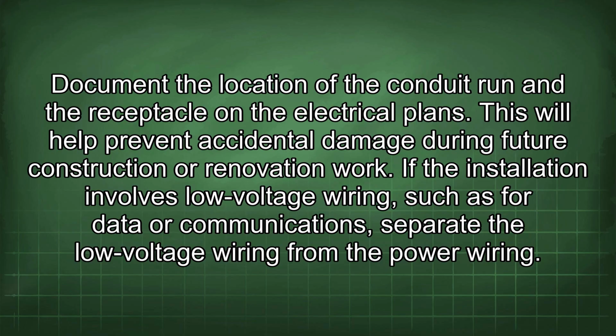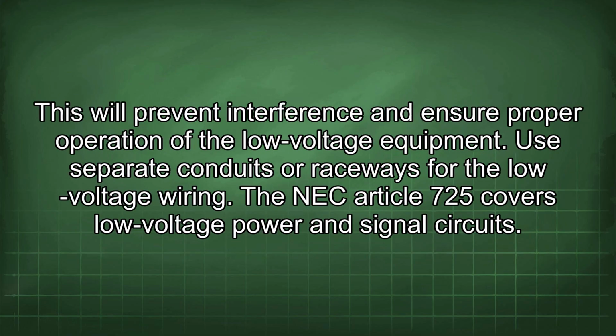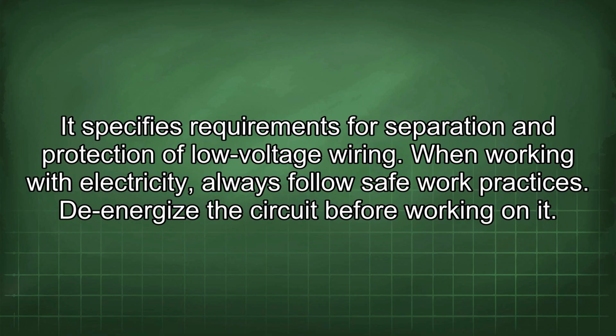Document the location of the conduit run and the receptacle on the electrical plans. This will help prevent accidental damage during future construction or renovation work. If the installation involves low voltage wiring, such as for data or communications, separate the low voltage wiring from the power wiring. This will prevent interference and ensure proper operation of the low voltage equipment. Use separate conduits or raceways for the low voltage wiring. The NEC Article 725 covers low voltage power and signal circuits. It specifies requirements for separation and protection of low voltage wiring.